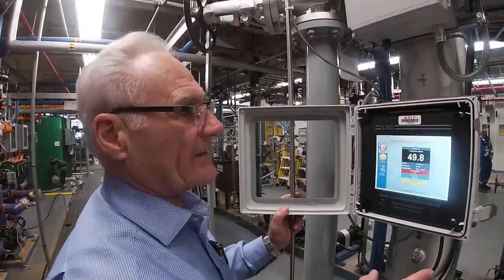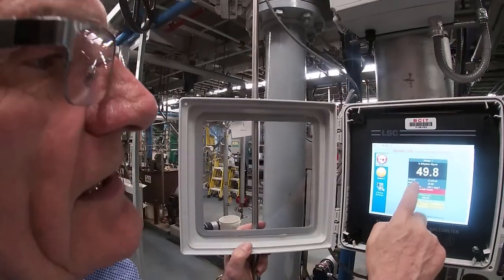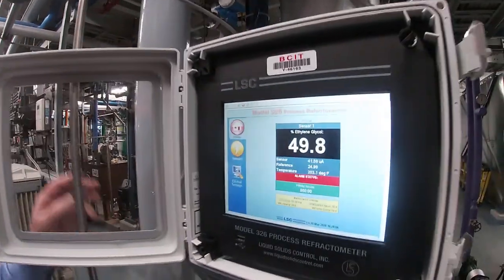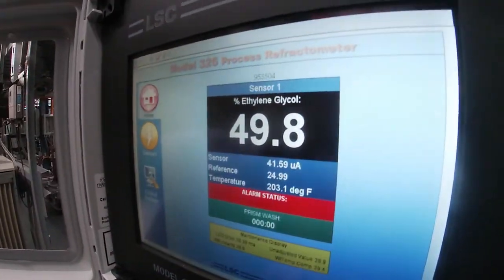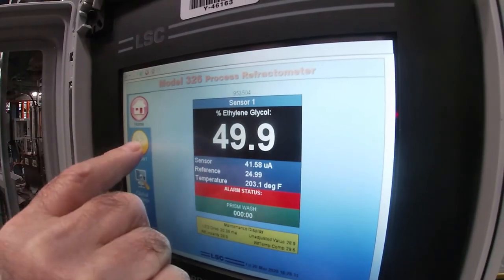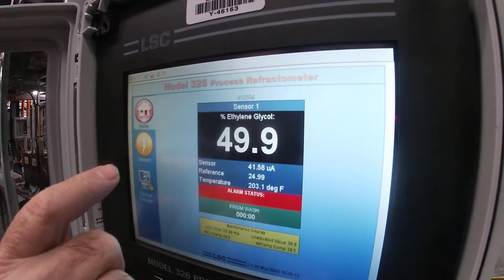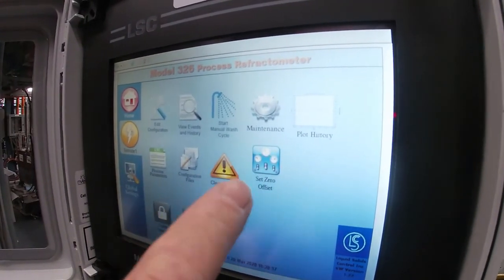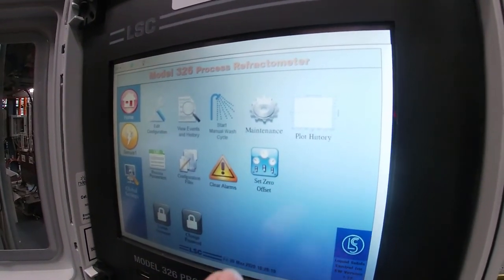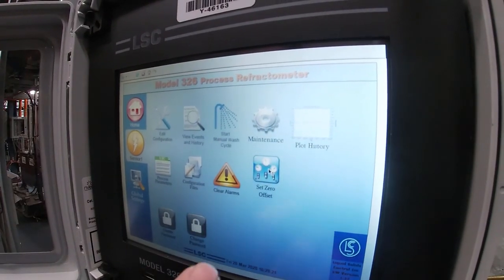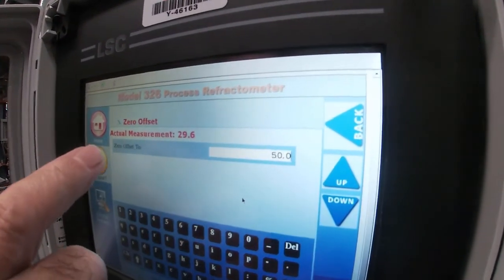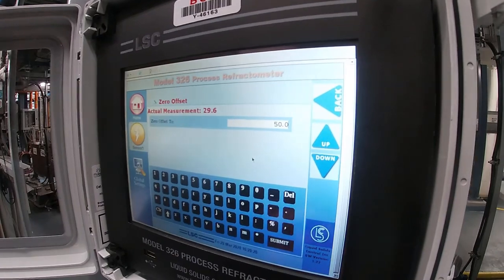So now we need to go back to the refractometer electronics and change the offset to get ourselves to 47%. The refractometer electronics page is right now reading 49.8. We just said it is 47. So we're going to go into sensor. And in sensor we got something called set zero offset. So we're going to select set zero offset, and it wants us to offset it to what number.